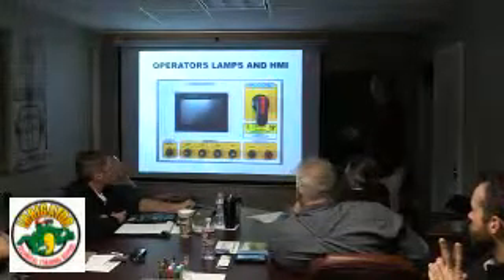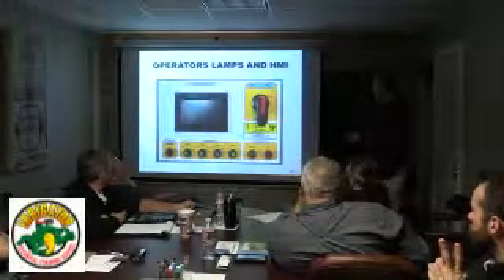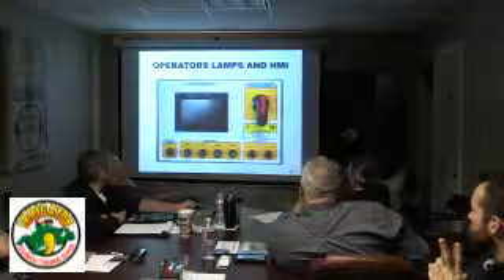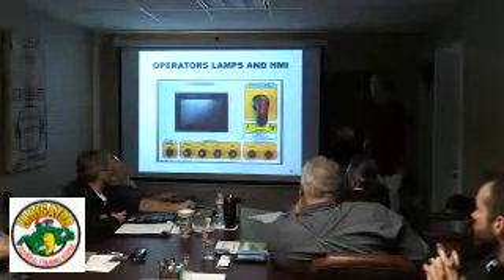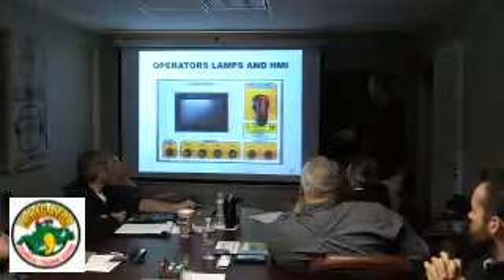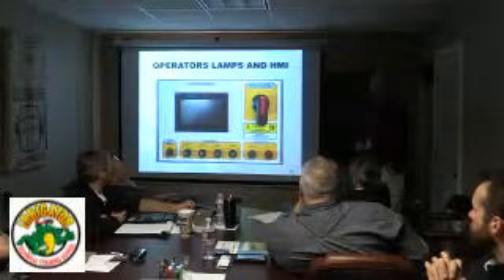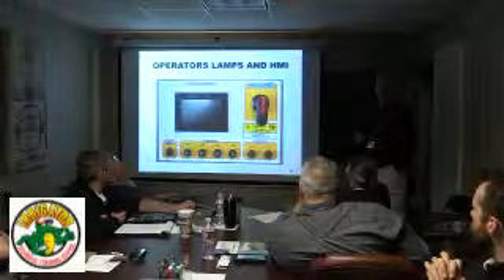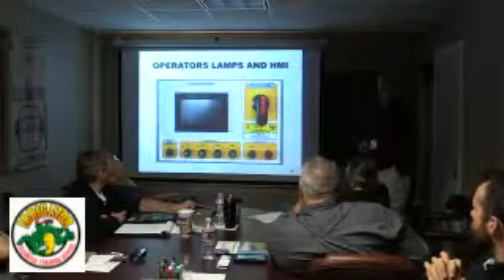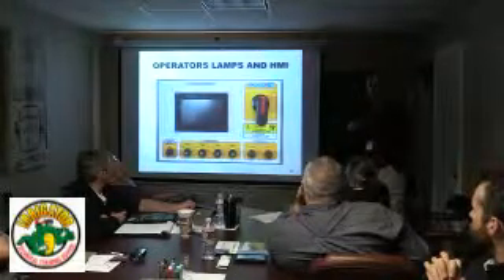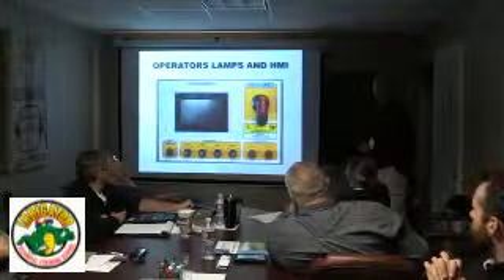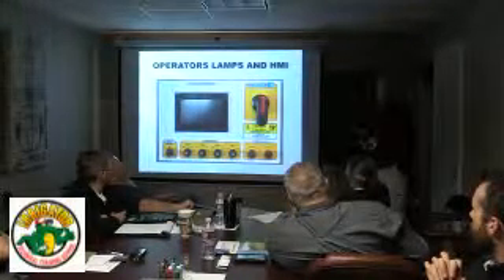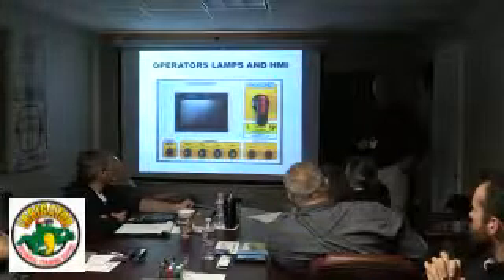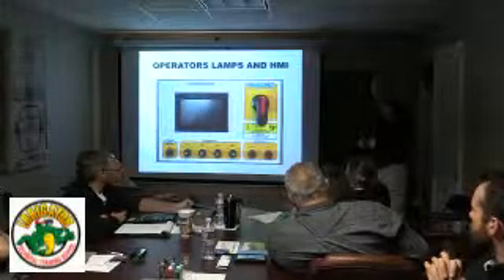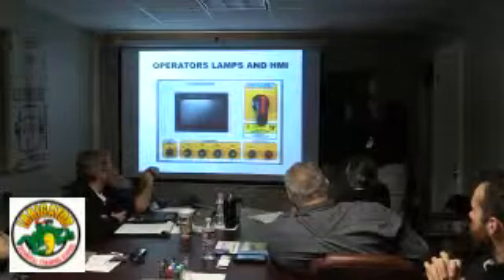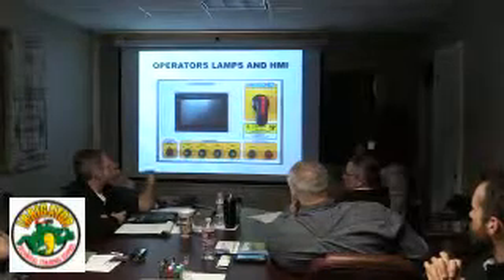So what I wanted to show is, you'll notice that almost all of our main disconnect handles are this ABB style. This has a small button that sits right here next to that O. It's on the off. It's hard to see. You have to get right up there and look at it. It's flush with the sides, about 1/8 inch round diameter, so you can't really see it, but if you have a small screwdriver or something, you can depress that button. It'll release the handle, and you can open it without turning the power off.